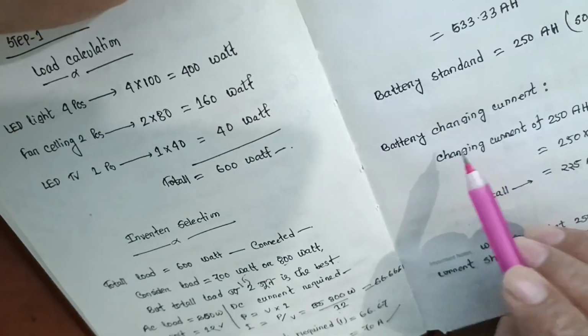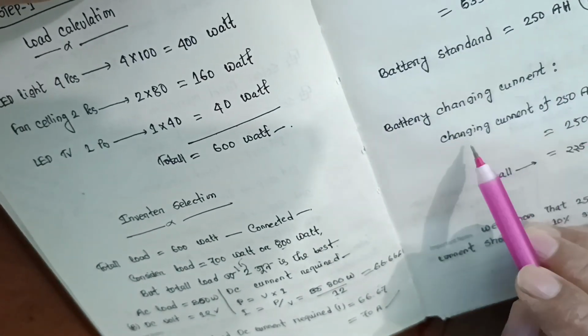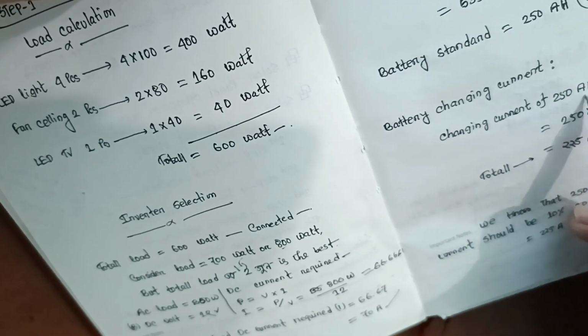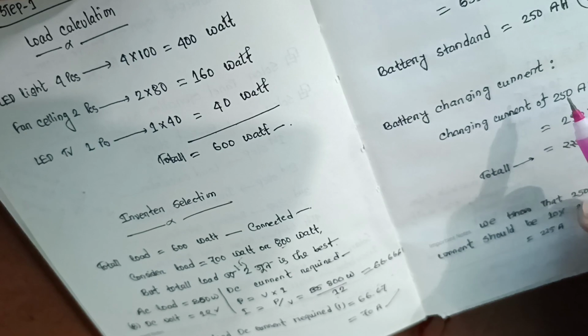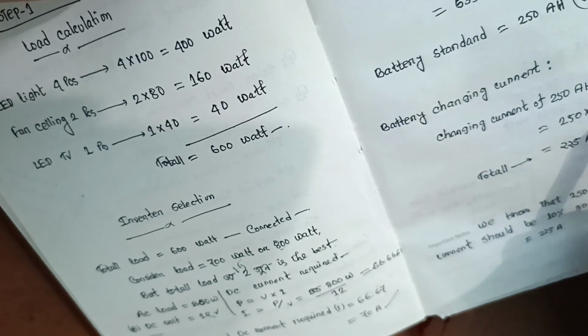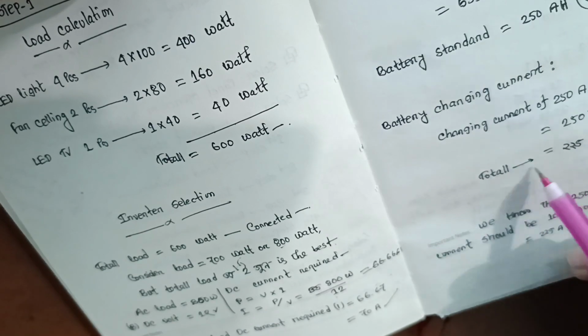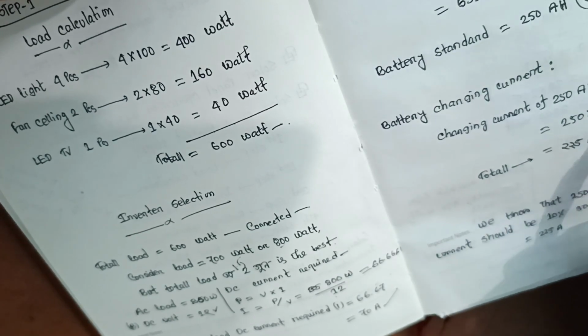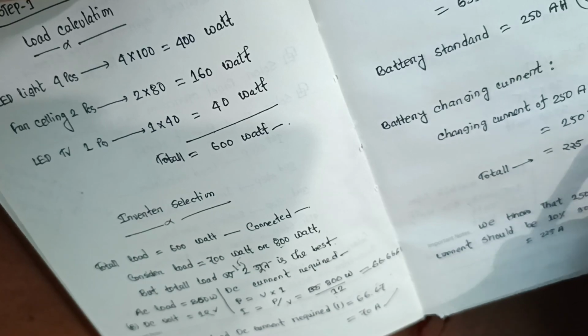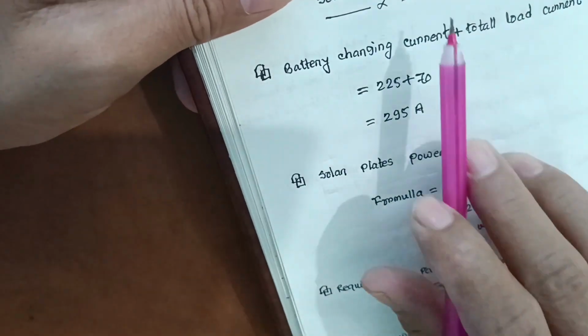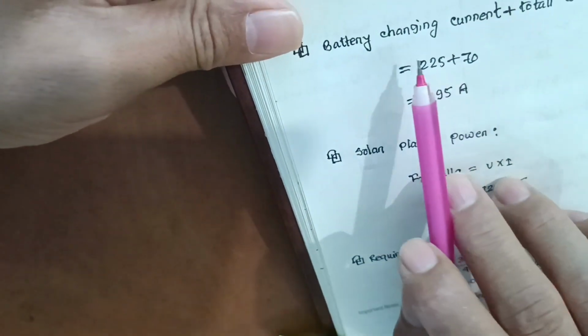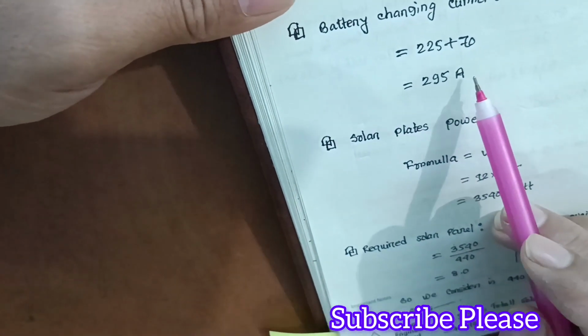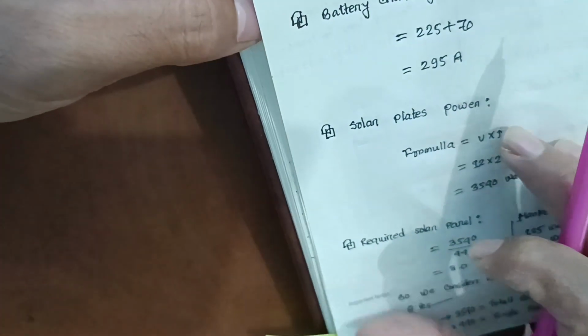Now the battery charging current required for the solar panel system. The charging current of a 250 ampere hour battery individually is 250 into 10%, and for 3 batteries multiplied by 3, the total is 75 amperes for battery charging current required for 3 batteries. So now the last step, the solar panel. The solar panel current is the battery charging current plus total load current, that is 75 plus 70, which is 145 amperes for this 800 watt solar project system.